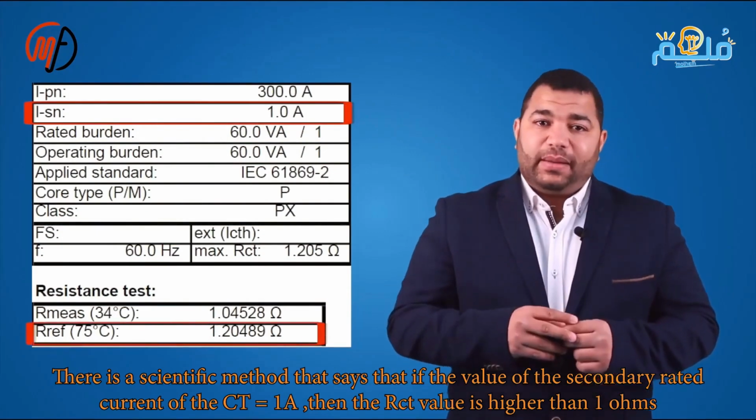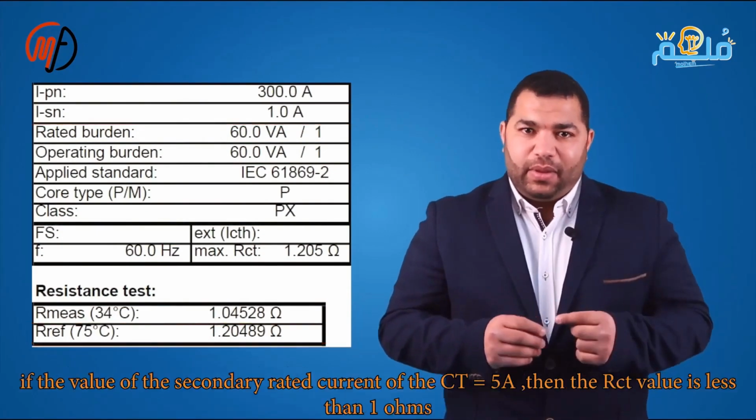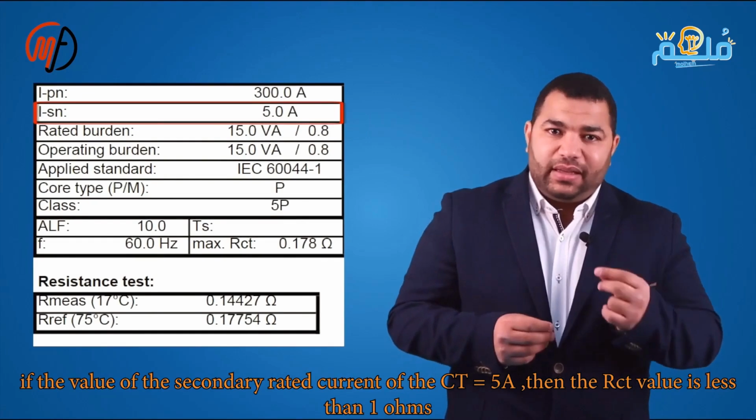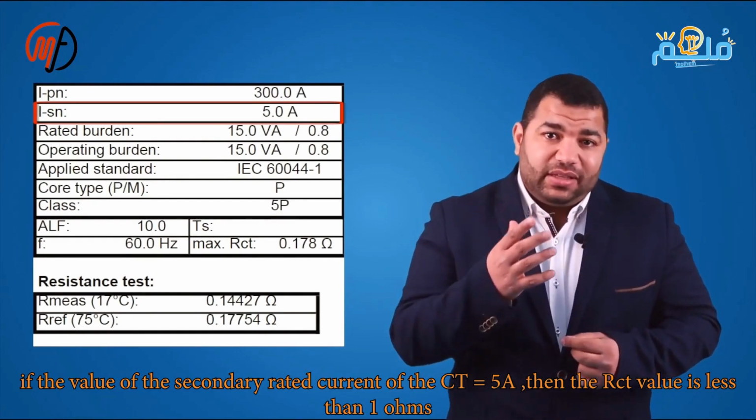What's the problem if we skip it? The RCT is crucial to calculate the burden on the current transformer, part of the circuit. Excluding it in the test adds excess load, risking CT saturation.